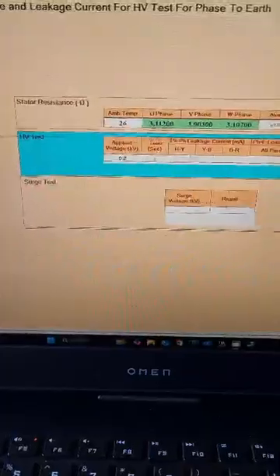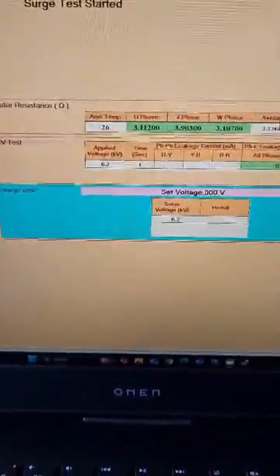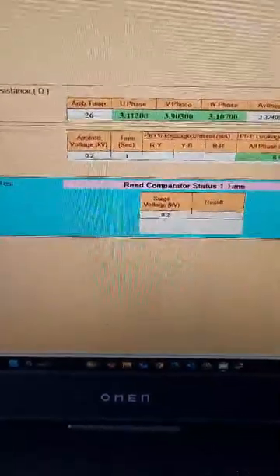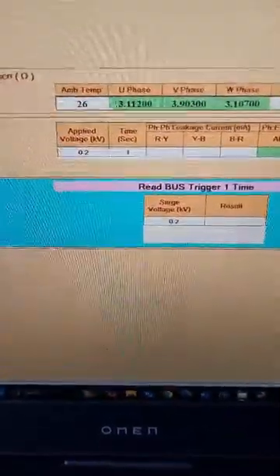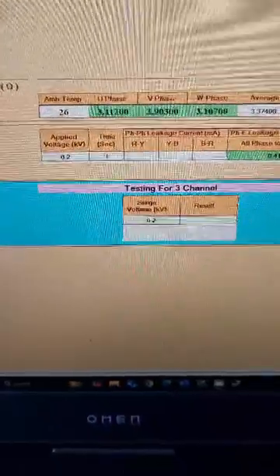Then the HV test is conducted, wherein you can see the applied voltage set at 200 volts in this particular case, and that also measurement for the leakage current has taken place. The third test is being conducted automatically, one by one in sequence. All this happens. Surge test, and the surge voltage applied is also 200 volts in this particular case.